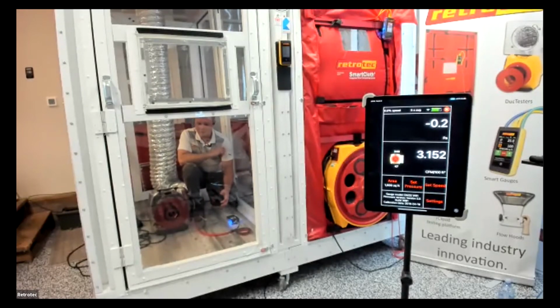So if you recall, we're canceling out a good chunk of the leakage here. Any leakage coming in from that duct system to the interior space is not included in this result. So it's always going to be a lower number compared to a total leakage test, which is why it told me that I needed to go down a size. So a lot of times when we do this duct leakage to the outside test, that's going to happen. You're just going to need to go down a range size in order to generate enough pressure inside the fan to get a reading here. So it looks like a little over 3%, 3.15% leakage to the outside is what we're getting here.